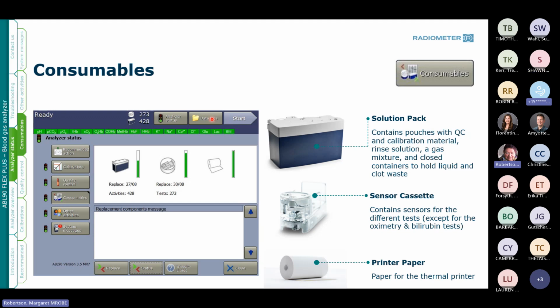Okay, so now we'll get into the consumables. There are only 3 consumables that need to be replaced on the ABL90. Those are, of course, the solution pack, which contains the QC material, calibration material, rinse solution, and the gas mixture. It's closed and it holds liquid and takes waste. The second part is the sensor cassette, which our tests are done on. And the last part, of course, is the printer paper.